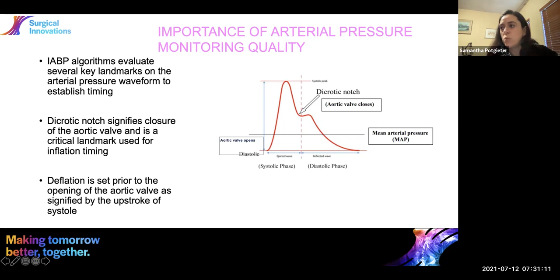So the algorithms in the machine, in the pump software, evaluate several key landmarks on the arterial pressure waveform to establish the timing. So our dicrotic notch signifies the closure of the aortic valve, and that's one of the critical landmarks that the algorithm looks for in terms of inflation. And deflation is set prior to the opening of the aortic valve, as signified by the upstroke in systole. So that's the R wave that it looks for and where it will deflate.